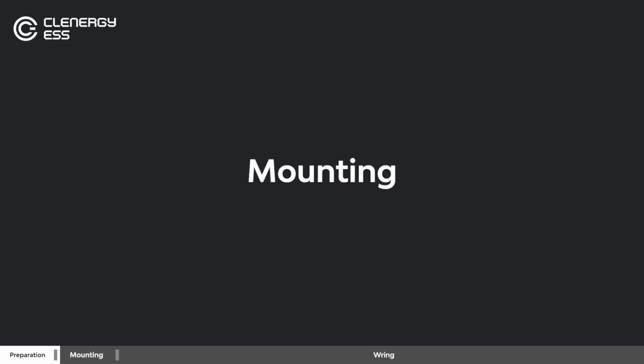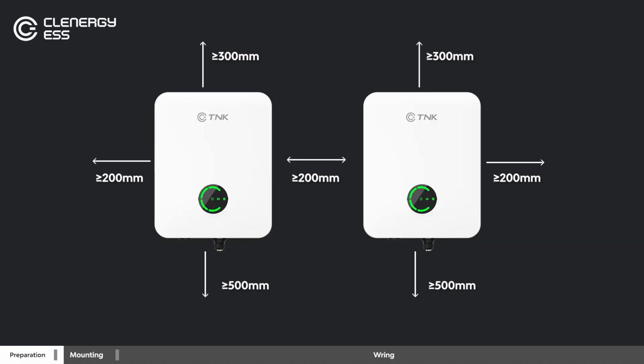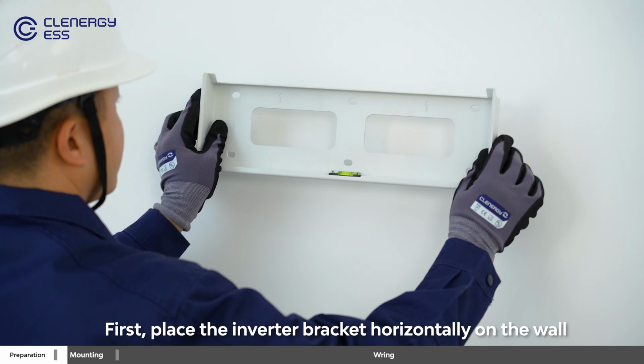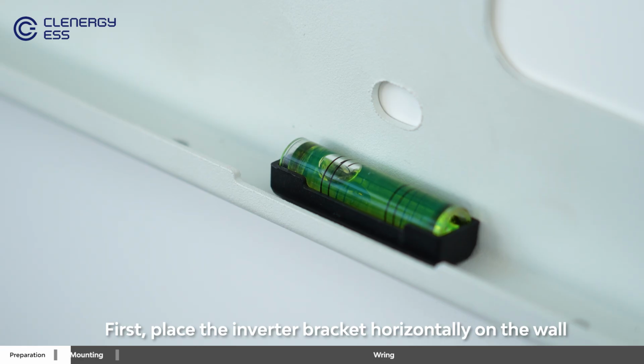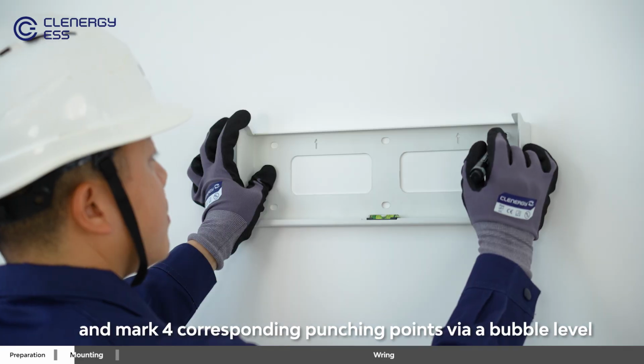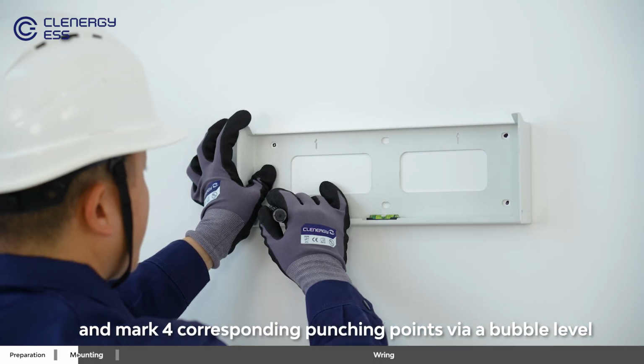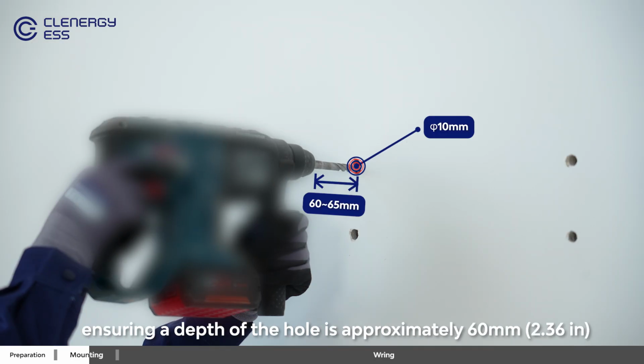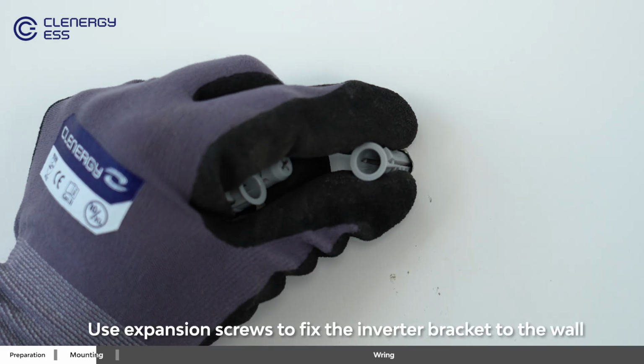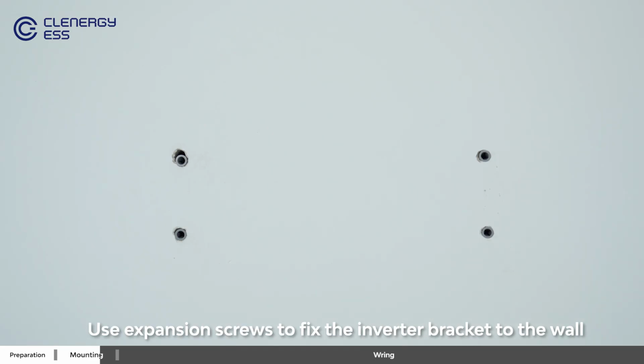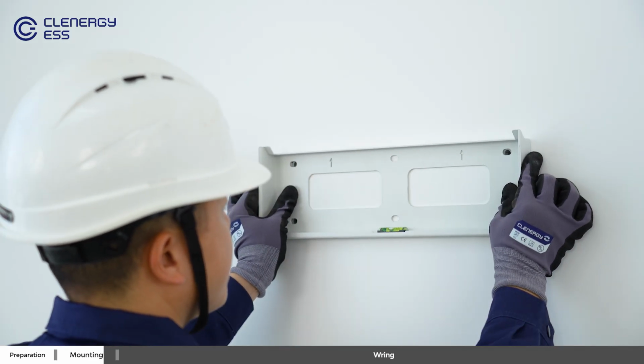Mounting. First, place the inverter bracket horizontally on the wall and mark 4 corresponding punching points via a bubble level. Use an impact drill with a diameter of 10 mm to drill the holes, ensuring a depth of the hole is approximately 60 mm. Use expansion screws to fix the inverter bracket to the wall.